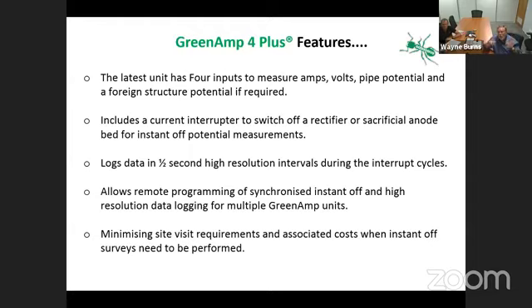They're all GPS synchronized, so you can monitor current. You can monitor the thing turning on and off down to half a second if you want. You can pre-program this, and monitor amps, volts, pipe potential, foreign structure potential. There's also a 5th channel, the contactor relay that turns the system on and off. This can be set to operate for a certain time frame and then default back to its normal operating conditions.